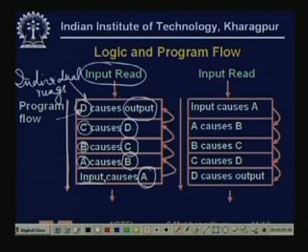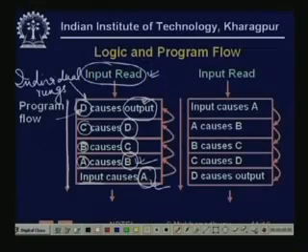In the next cycle, this changed value of A will cause a change in B, while C and D will still remain unchanged, and the output will still remain unchanged. So in this way, just because we have organized these programs in this fashion, we will get a 5 scan cycle delay between an input read and an output change, which is completely unnecessary, because if we had organized it in a slightly different way, then what would have happened?